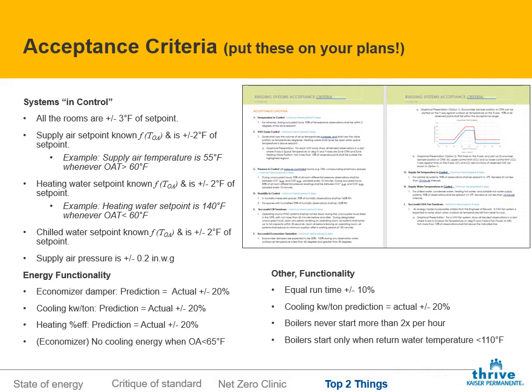You should see systems ramp up and ramp down according to outside air temperature, right? Those should all come right out in the data, and the data should prove that they're working the way they're supposed to be working, right?